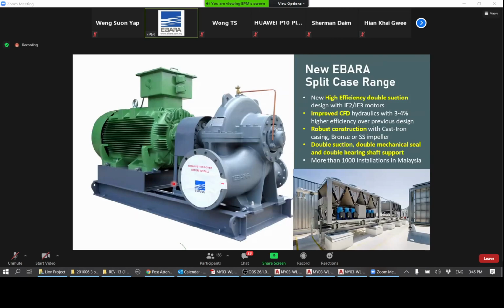Our split case pump has also been redesigned with a new volute design using CFD, and in a lot of applications we offer it with either IE2 or IE3 motors for improved energy savings. Not only that, but as mentioned before, with the double suction, double mechanical seal and double bearing, it is a very well balanced pump. To date, we have more than 1,000 installations in Malaysia alone, especially in aircon applications.